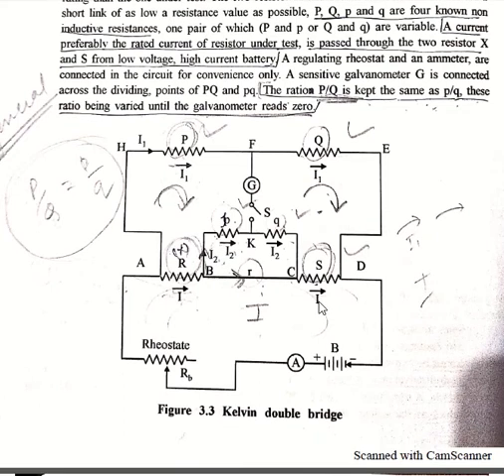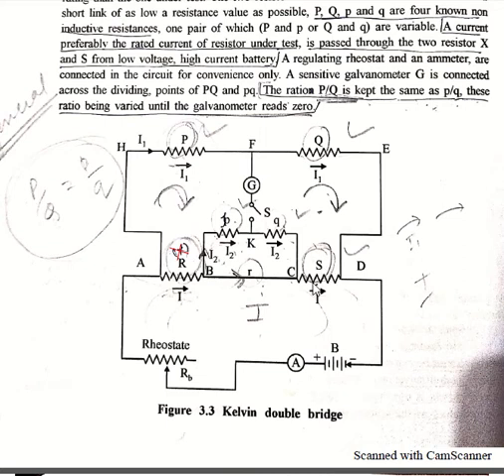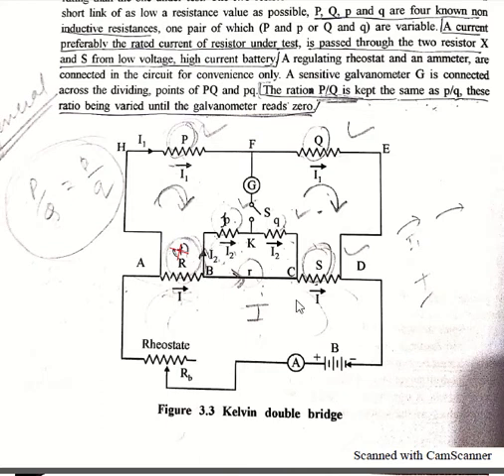Now coming to the diagram of this Kelvin Double Bridge method. In this diagram we have X, which is the resistor under test, and S is the standard resistance. As in our previous case of potentiometer, we have two conditions: the resistance of S should be of the order of the resistance under test, and the second condition is its current rating should be the same or of higher current rating than resistance X. These two resistors X and S are connected in series with a short link.